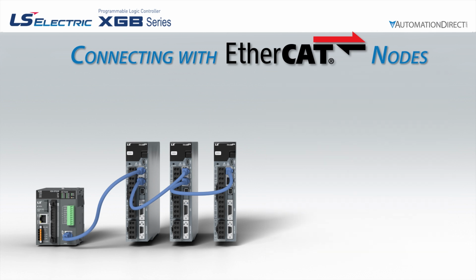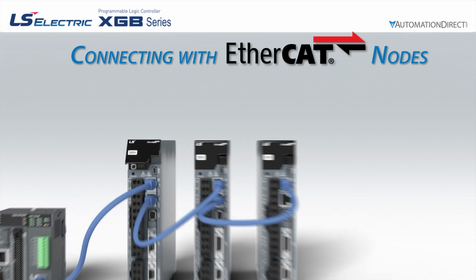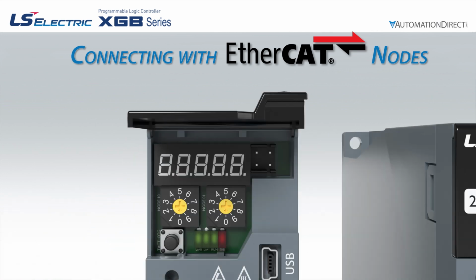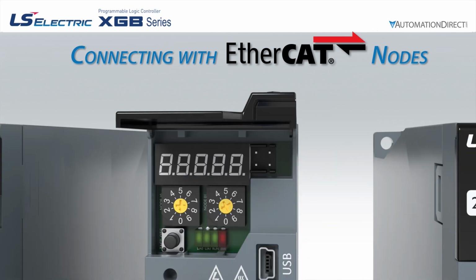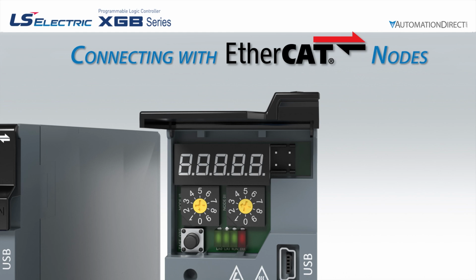Remember that we are building a 3-axis motion system that will have an X, a Y, and a Z axis working together as part of a tabletop gantry system. We have manually set the node ID rotary switches to node 1 for the first drive, the X axis, node 2 for the second drive, the Y axis, and node 3 for the third drive, which will be the Z axis.